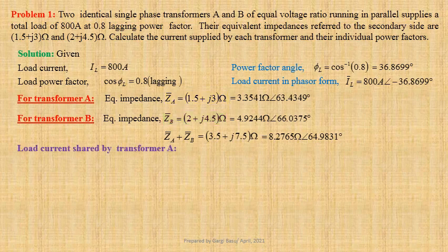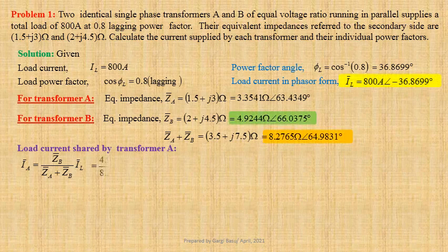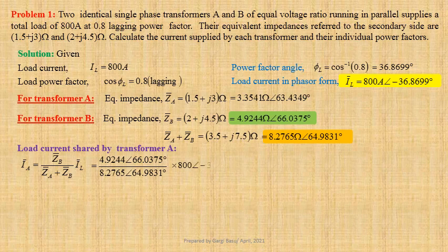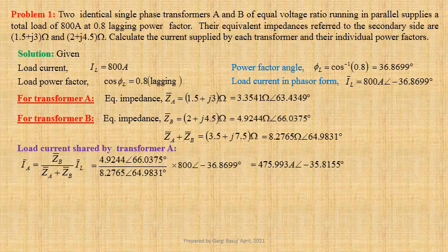Let us now determine load current shared by transformer A. IA equals ZB divided by ZA plus ZB, into IL. Using values we get 4.9244 ohm at an angle 66.0375 degree, divided by 8.2765 ohm at an angle 64.9831 degree, into 800 at an angle minus 36.8699 degree. That gives us 475.993 ampere at an angle minus 35.8155 degree.